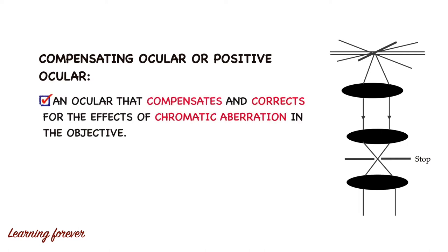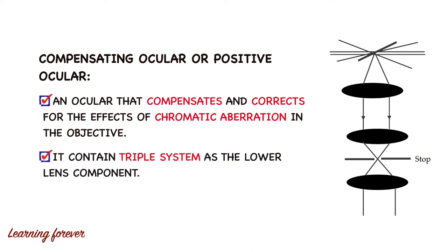The third type is the compensating ocular, also called a positive ocular. This ocular compensates and corrects for the effect of chromatic aberration in the objective. Chromatic aberration is the failure of a lens to focus all colors to the same point. The earlier two systems — Ramsden and Huygenian — are unable to correct for chromatic aberration. Therefore, in the compensating ocular, one more lens has been added, giving it a triple lens system as the lower lens component.